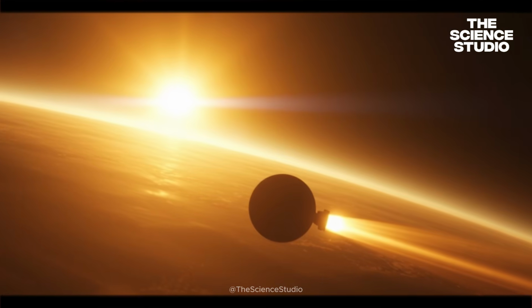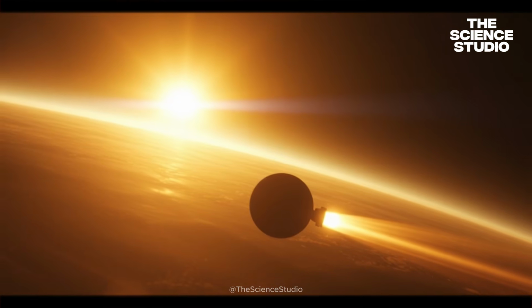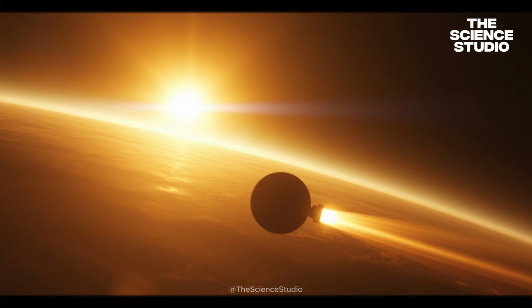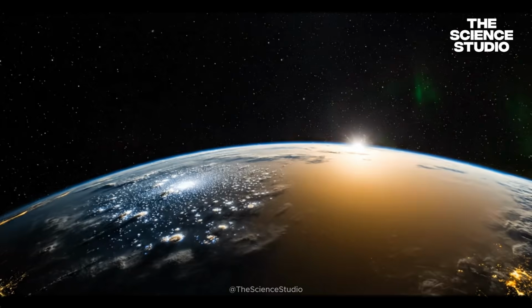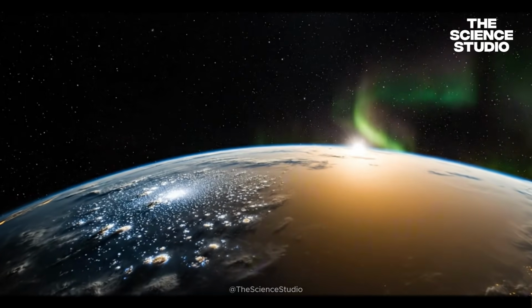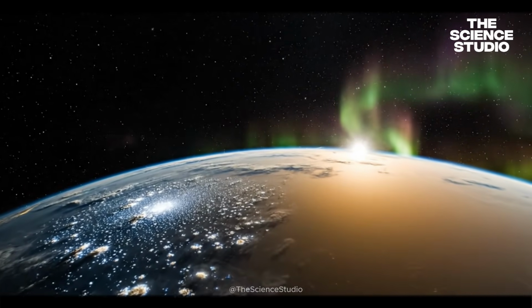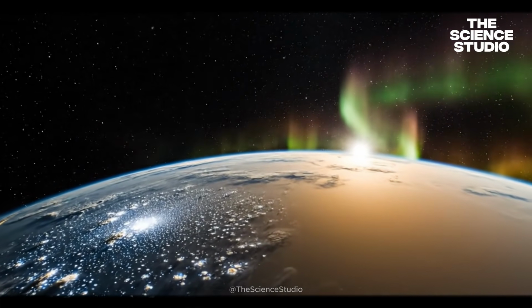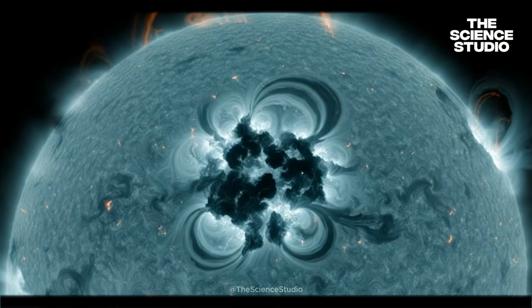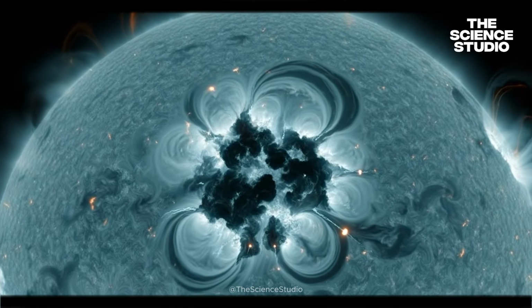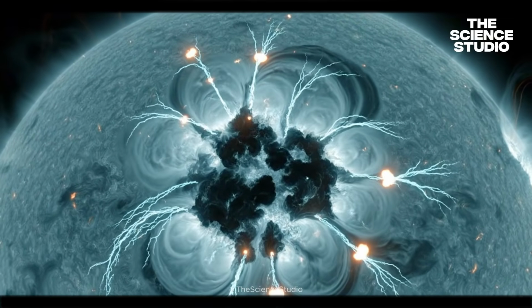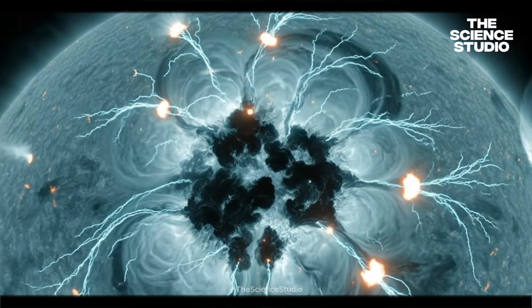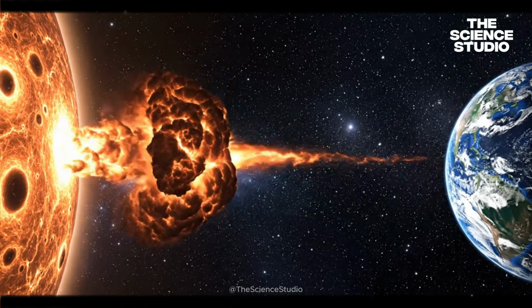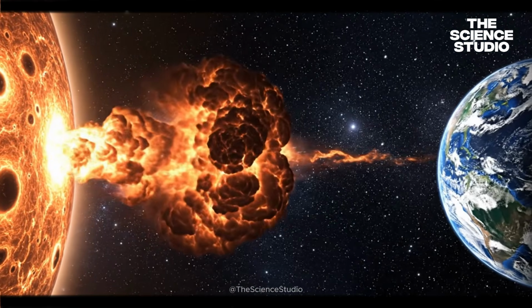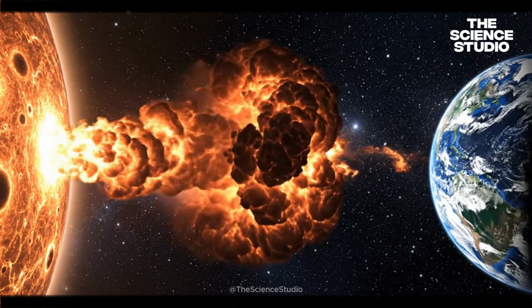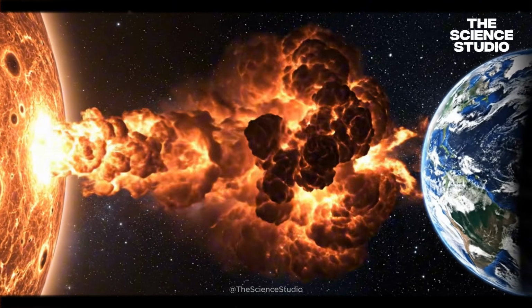For context, 9.4 gigawatts is roughly the electrical output of 9 large nuclear reactors running at full power, delivered to a grid not designed to absorb it in under 90 seconds. That figure is the worst-case ground-level consequence of a geomagnetic storm on record in North America. This April event didn't approach that figure. It wasn't supposed to. G2 is several steps below G4 on the KP scale, and the grid absorbed the induced current inside its normal operating margin.